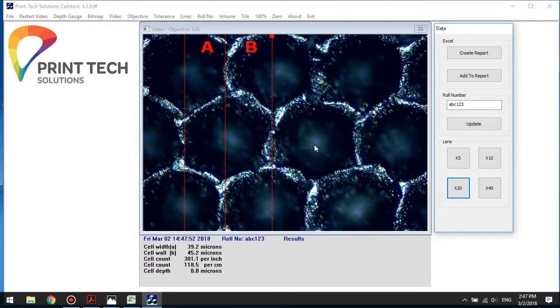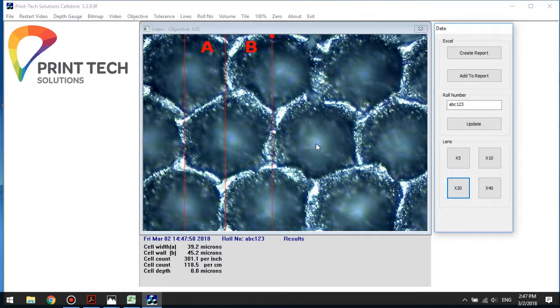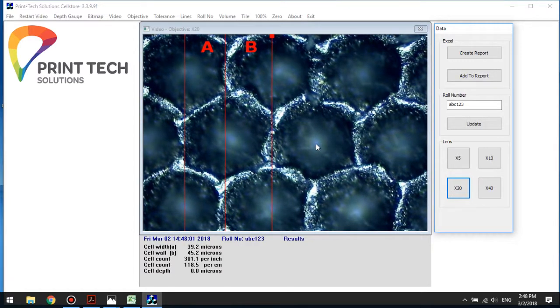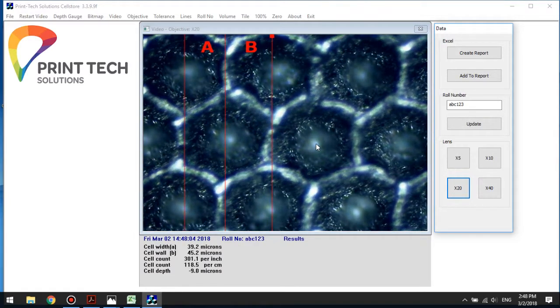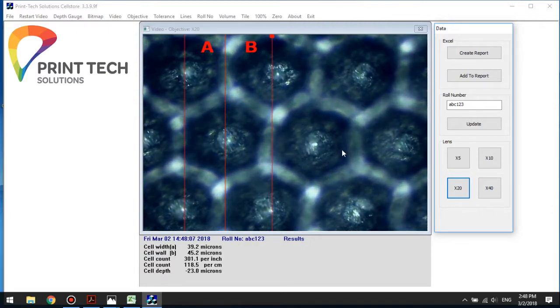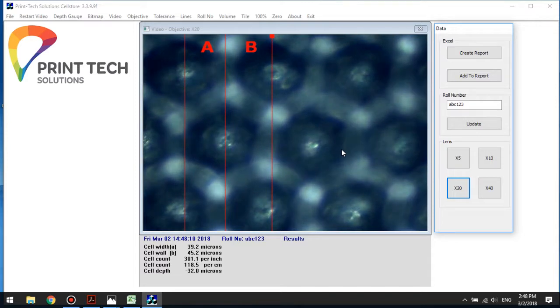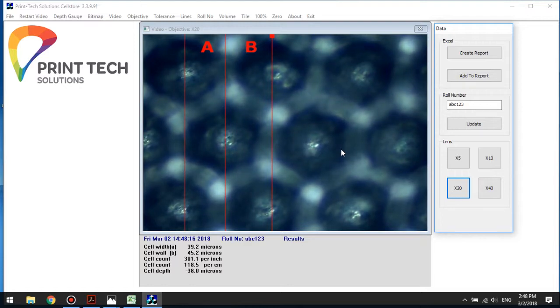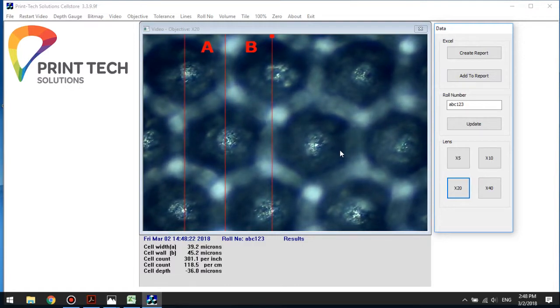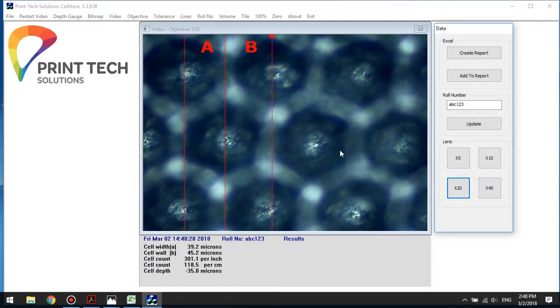The next thing I'm going to do is focus at the bottom of the cell. When I focus down to the bottom of the cell, I'm actually going to go beyond the bottom so it's out of focus, and then I'm going to come back, and the first thing I see that's in focus I'm going to use as the bottom of my cell. So now we have a reading of 35 microns — cell depth, 35 microns.